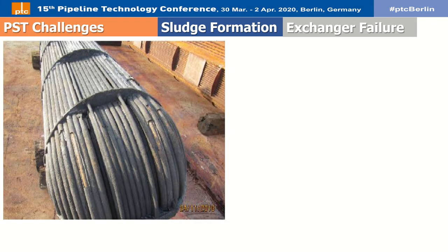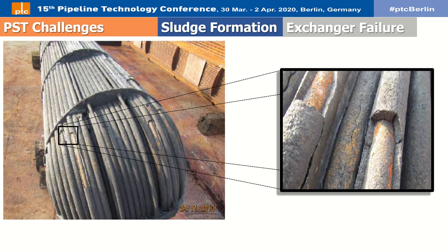Another difficulty with pH stabilization is sludge deposition due to contamination of glycol with salt, hydrocarbon, particulate, or corrosion inhibitor. These contingencies increase the cost for replacing glycol filter elements and create maintenance compliance challenges. High concentration of calcium ions in MEG can dramatically affect the MEG regeneration unit by causing scale precipitation on external and internal sides of exchanger tubes, hindering conversion of rich MEG to lean MEG within specification.